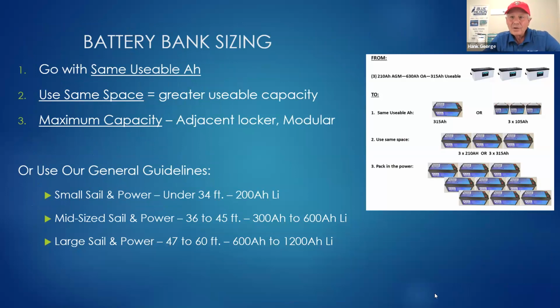If your battery bank AGM were, for example, three 210 amp hour AGMs, that's 630 amp hours total. 315, or 50%, would be usable amp hours, and that's just the nature of lead acid batteries. You got to be careful not to keep cycling it below 50% capacity, or right from the start you can be taking away significant life. So you'd have 315 amp hours usable.